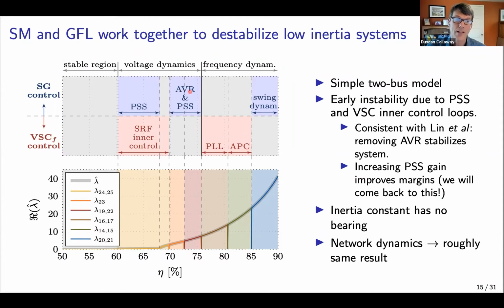The automatic voltage regulator starts to matter as well. As we get more penetration, frequency dynamics start to become important, and the phase lock loop also becomes implicated in these instabilities, as well as active power control. And then finally these Newtonian swing dynamics on the synchronous generator. So at very high penetration levels, all of these different control blocks matter, emerging in addition to the initial state variables in the instability. This implies there are potentially many different state variables we have to be concerned about in order to ensure the system is small signal stable if we want to guarantee that in the future.